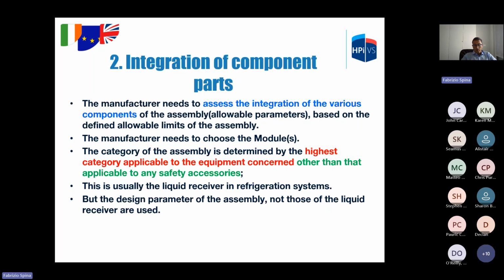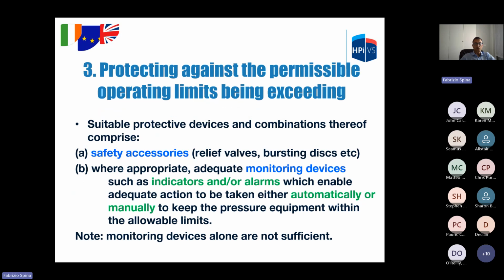The component with the higher category is usually the liquid receiver in a refrigeration system, but the design parameters of the assembly must be considered, not those of the liquid receiver. That means that a vessel category can be modified within the assembly evaluation. That is, the PS value can be reduced according to the safety device set pressure. This reduced PS may result in a lower category. We will see an example later.